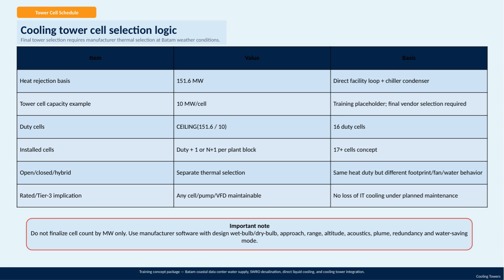It's important to note that cooling towers come in different types, open, closed, and hybrid, and while they handle the same heat duty, they vary significantly in terms of physical footprint, fan operations, and water behavior. The rated or Tier 3 implications mean any cell, pump, or variable frequency drive can be maintained without losing IT cooling capacity during planned maintenance, which is crucial for data center uptime.